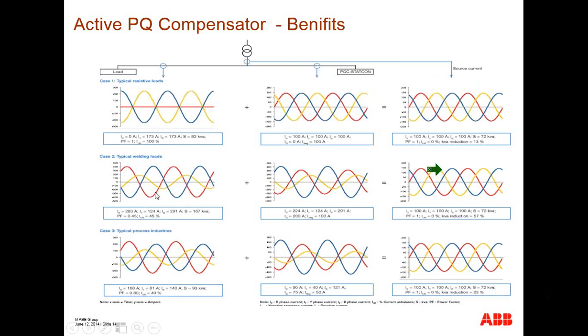Now, if you have different kinds of other applications where there can be 200 amps in R phase, 180 amps in Y phase, and 300 amps in B phase. This is the type of compensator current which is generated, the anti-current, and this can also be compensated by means of this active compensator. So you can see in all three cases that whatever the nature of the load, whether it's a two-phase load, or unbalanced inductive, or unbalanced capacitive, in all three conditions the incoming current from the grid is always the same: balanced and active power only.